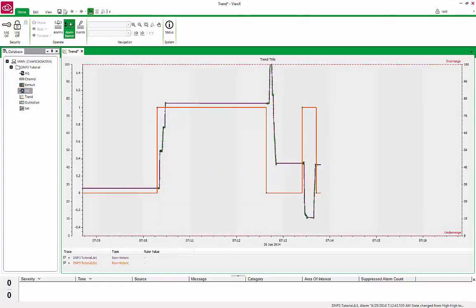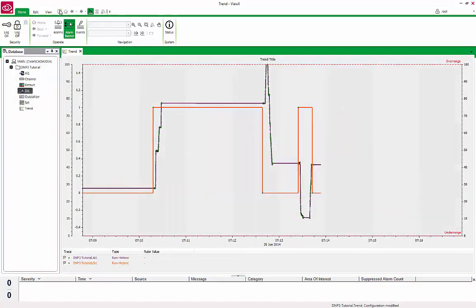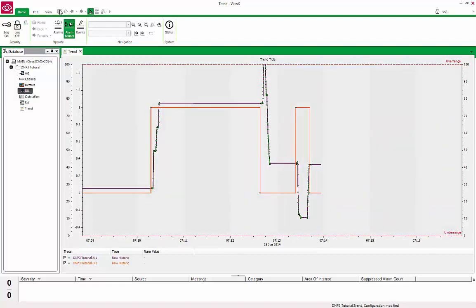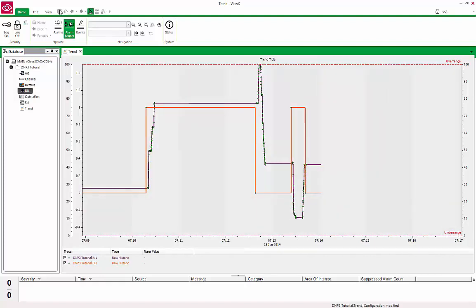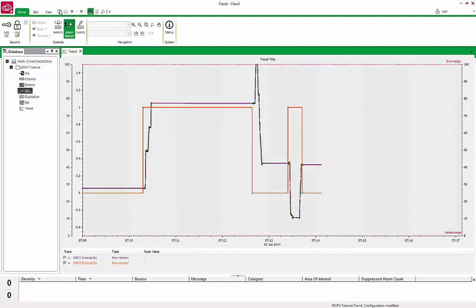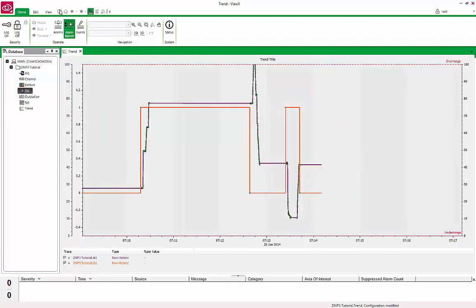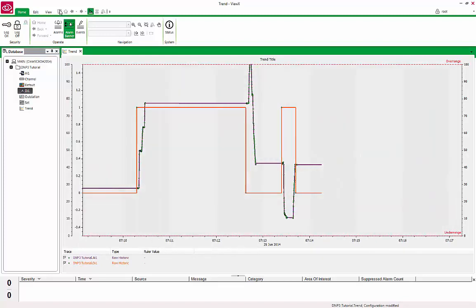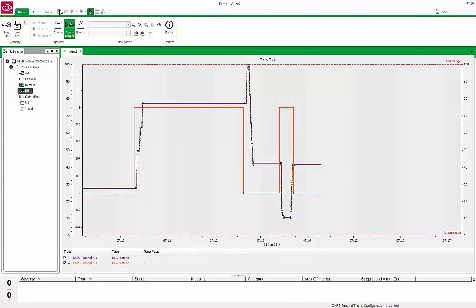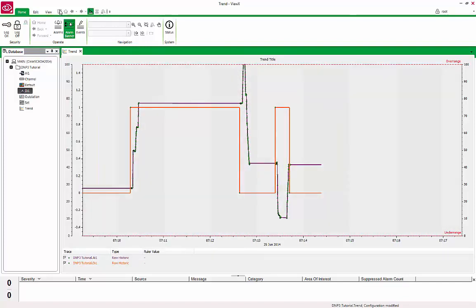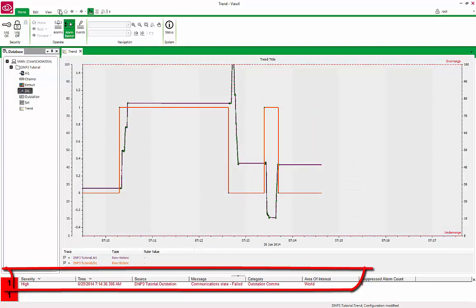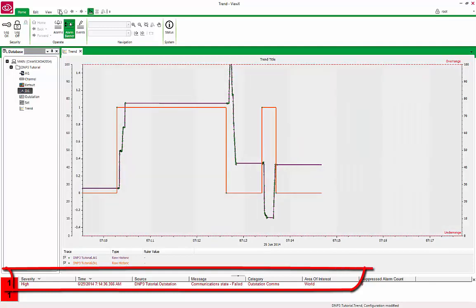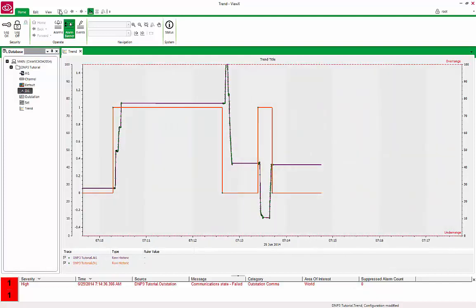And before we finish, let's have a look at what happens when communications is lost to the device. Unplug the communication cable from the device. After some time, ClearSCADA will raise a communications failed alarm. The time to raise this alarm depends how frequently you poll the device, the communication retries configured, the number of transaction attempts, and the way that the failure occurs. All these settings are configurable to provide flexibility in the way that communication problems are reported to users. Notice the communication failure alarm in the alarm banner. Go ahead and change the values a few times. After a short period, plug the communications cable back in.